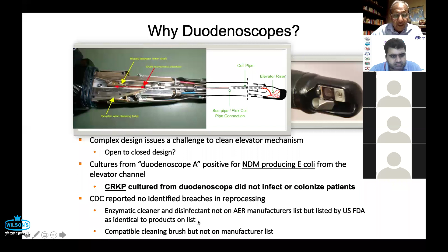And cultures from the duodenoscope were positive for NDM-producing E. coli from the elevator channel. This is the elevator channel. And there was no identified breach in the reprocessing, as I said earlier, and a compatible cleaning brush was used, but it was not on the manufacturer list. So the possible mechanism is that the fixed distal cap failed to allow adequate cleaning and disinfection. And this O-ring, which is provided there, may not seal the forceps elevator axis sufficiently. These new duodenoscopes were then withdrawn.